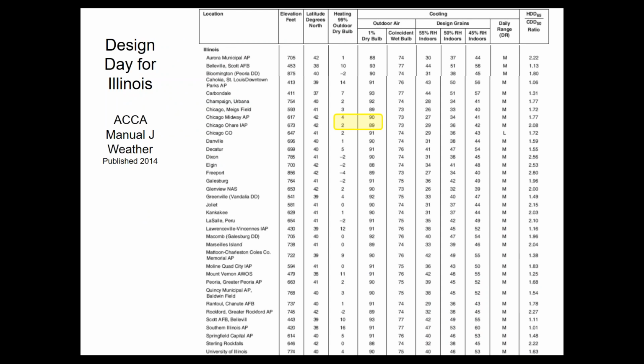ACCA Manual J also specifies the outdoor conditions that I have to use. So I'm looking in Chicago at O'Hare Airport, just as an example. For heating, I can design for 2 degrees outside and for cooling 89. I cannot use the traditional 95 and minus 10. That's not allowed. I'd have to use 89 and 2.